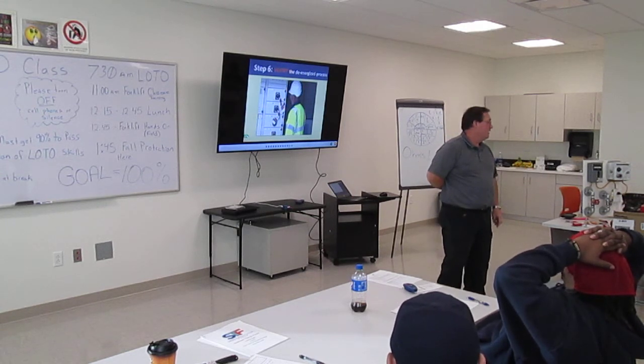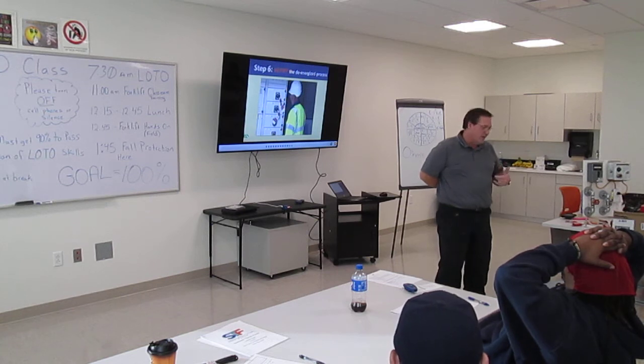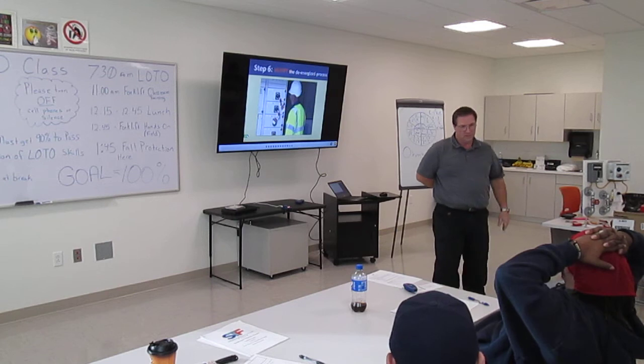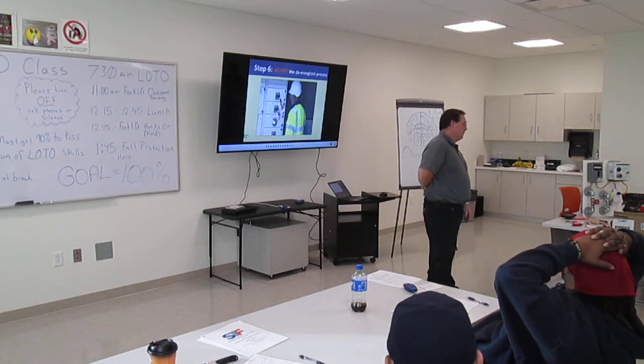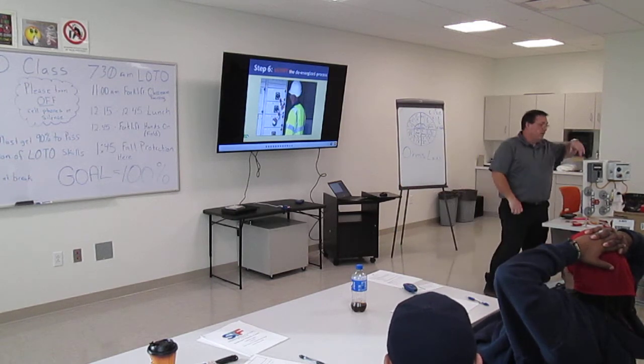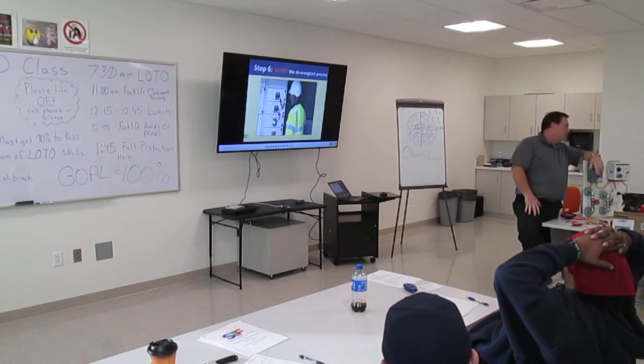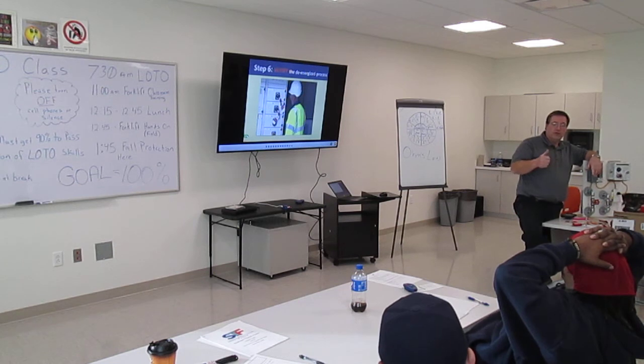So we go over there, we look at it, we take it apart with our gloves on, we put a meter on it. Sure enough, it's got 480 volts to it. So we go back up to the panel room, he's downstairs on the radio, and I'm upstairs on the radio, and we start flipping breakers. Nope, nope, nope, yep, that's it.